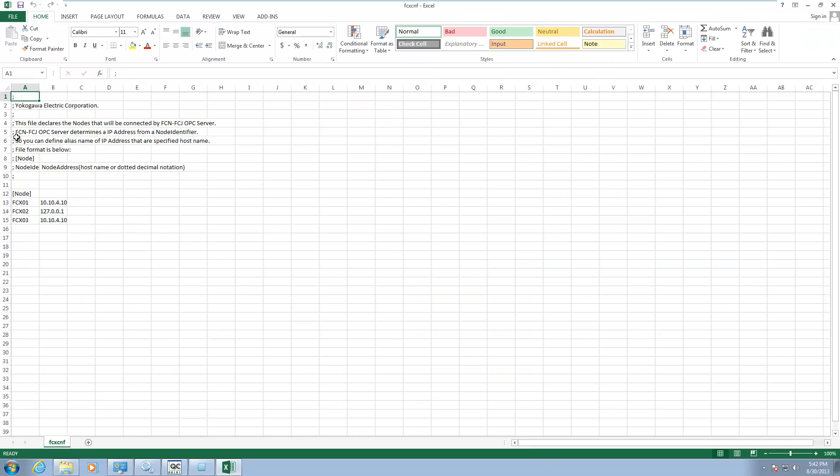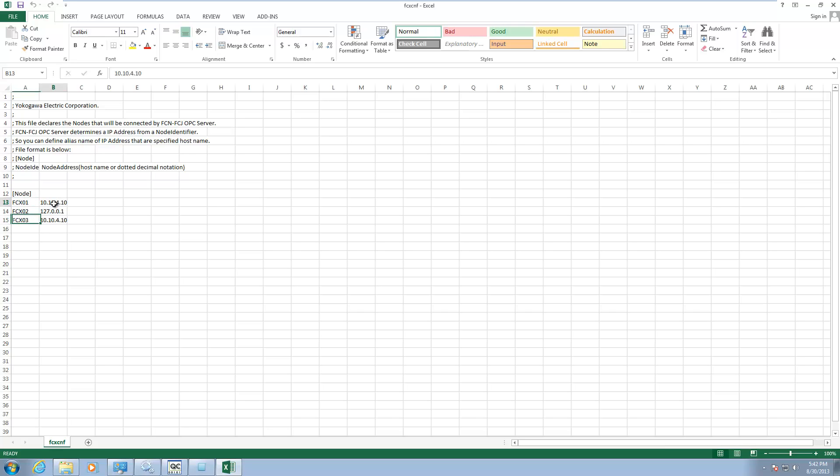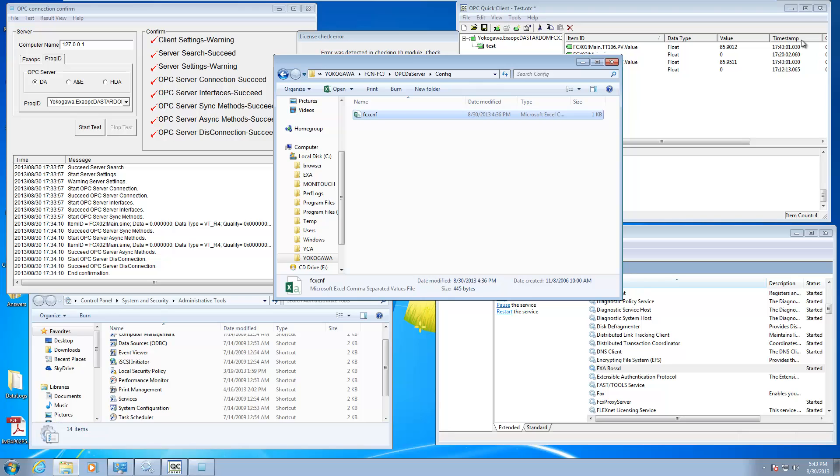In this file, you can see there are semi-colons. That denotes that that line is commented out. When you first get this file, you're going to see a commented out line. What you can do is you can give your Stardom units a name and then you put their corresponding IP addresses down. Once you do, these will become browsable within the Stardom OPC server. You've got to make sure you do this. It's a comma separated variable file. Make sure you leave it that way. Make sure you put these in and get rid of the semi-colon on it. You can name them whatever you want and just make sure they have a valid IP address corresponding to them.